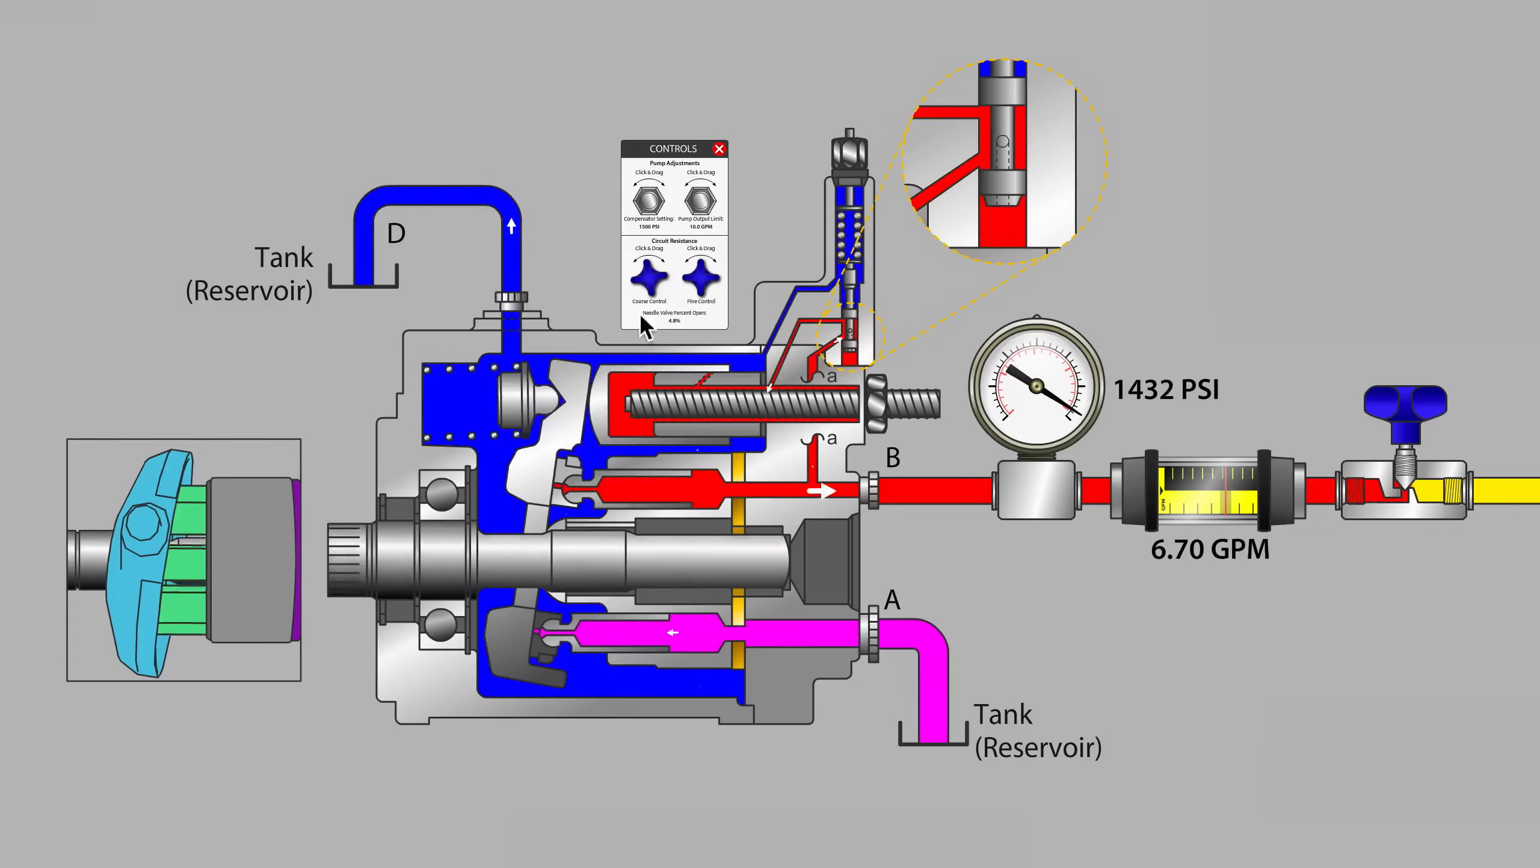In addition, blocked case drain line will cause our pressure compensator function to misbehave or cease entirely. The malfunction may be no pressure compensate function is available. So again the pump could easily move to a catastrophic state without maintaining case drain flow.